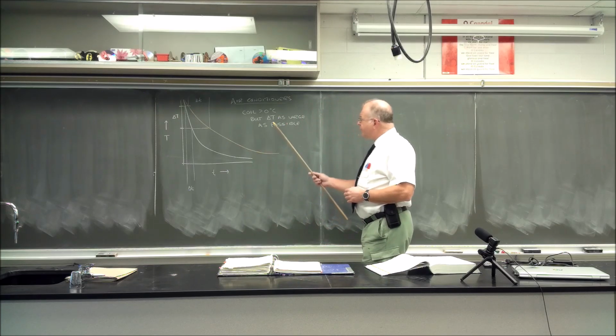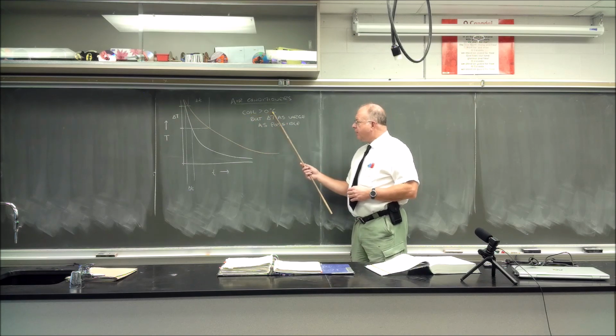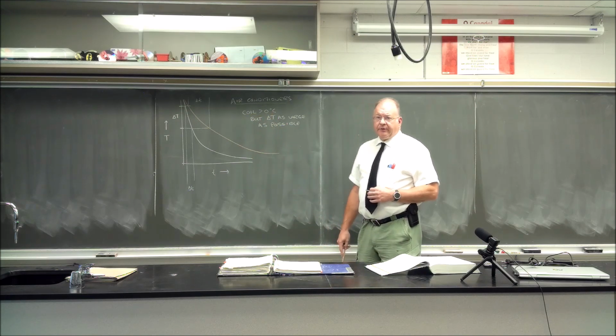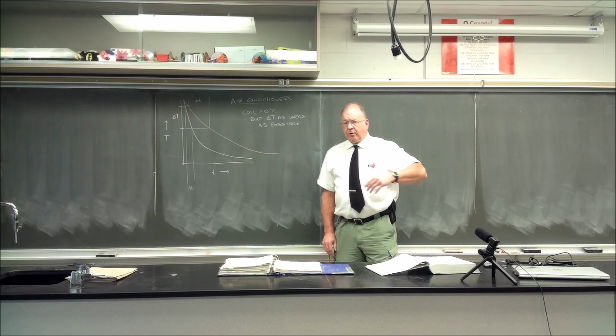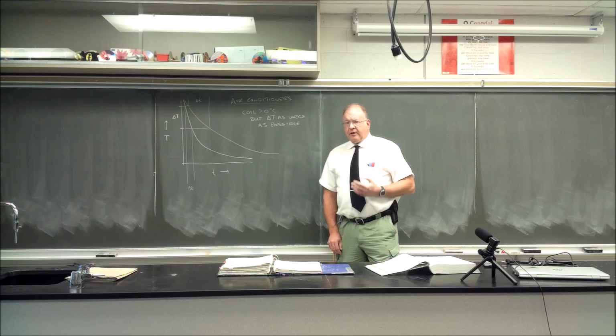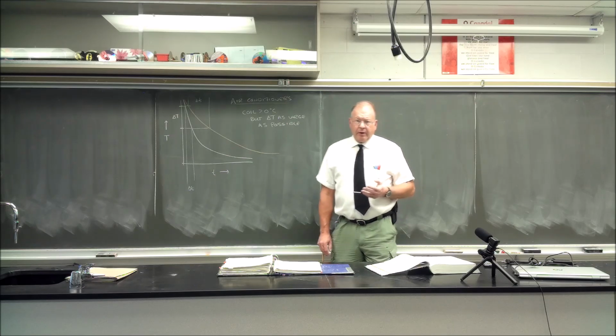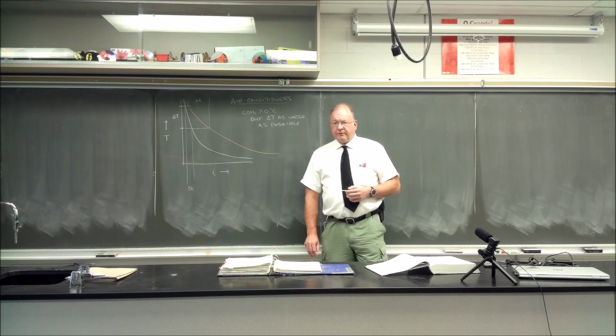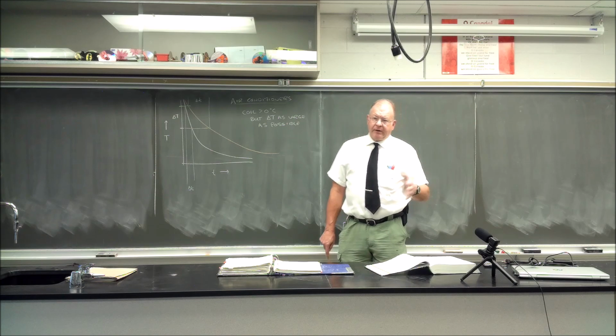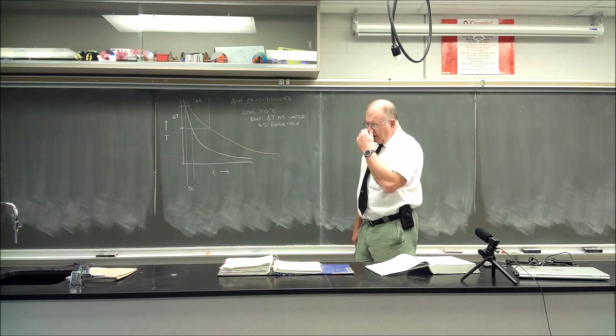So air conditioners, generally speaking, will want to have their coils above 0 degrees Celsius for the most part. Otherwise, the coil will freeze. Oftentimes in the summertime, the air is quite humid, so there'd be a fair amount of moisture collecting on the coil and causing icing, which can block passage of the air or require expensive, complicated heating systems that periodically melt the coil ice.